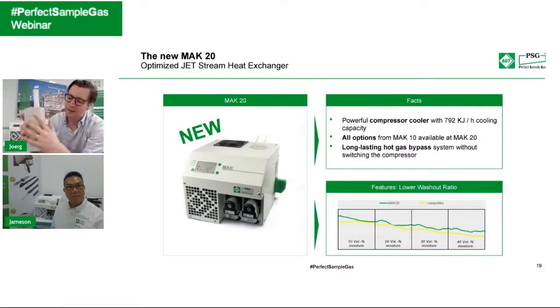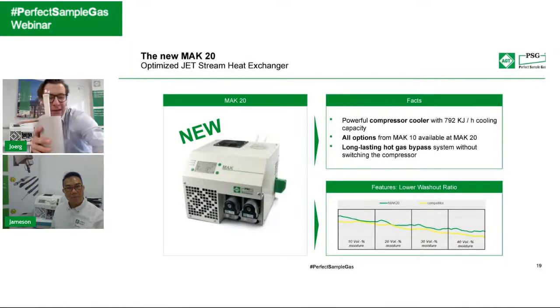This is the cooling block. Different to the heat exchanger technology we use in the MAK10, which I have here, the MAK20 uses a different technology, a so-called jet stream heat exchanger. The hot gas comes in here and the dry gas gets out here, and the cooling comes from the outside. This is the so-called cooling block.